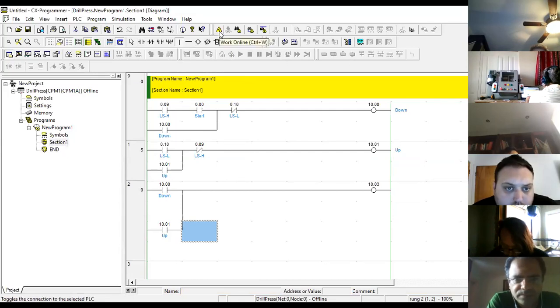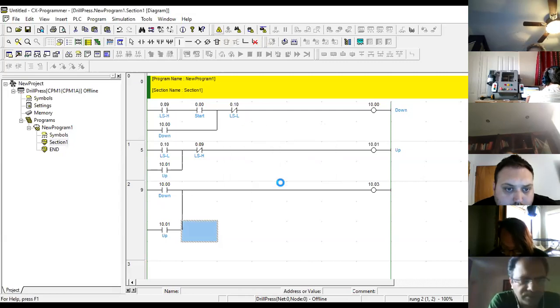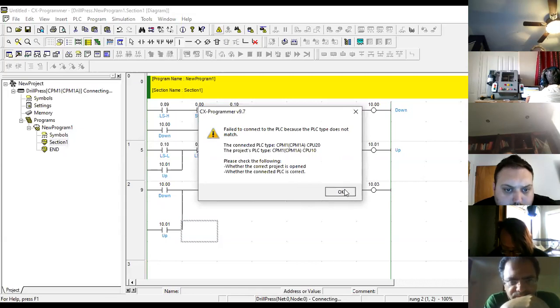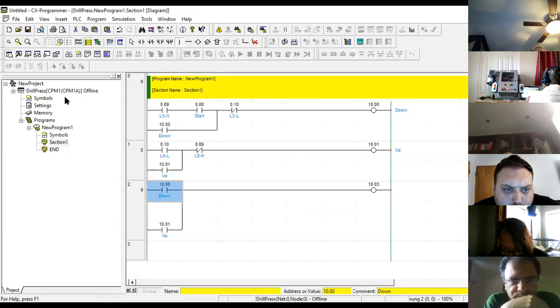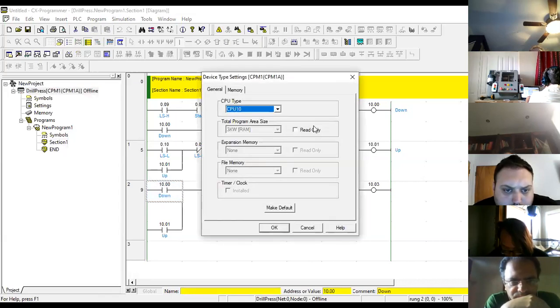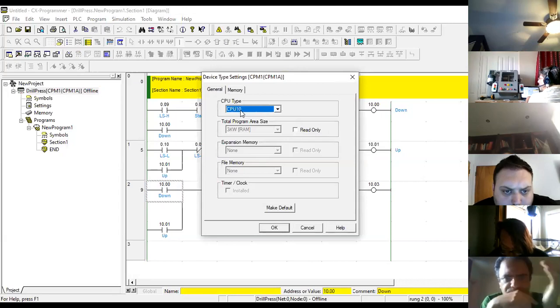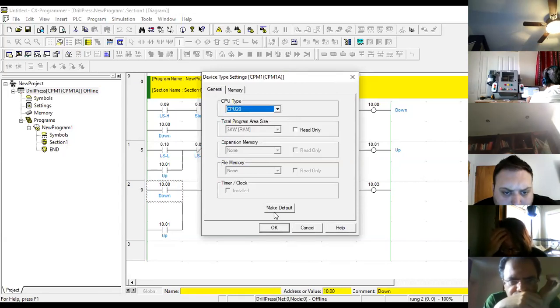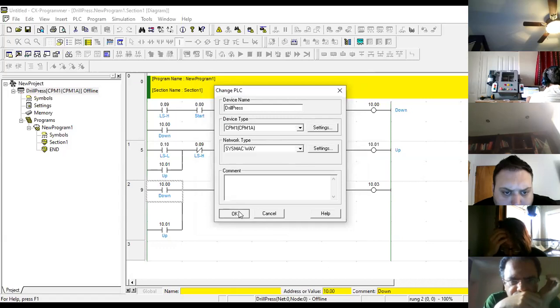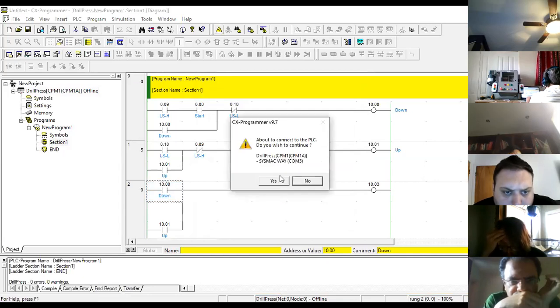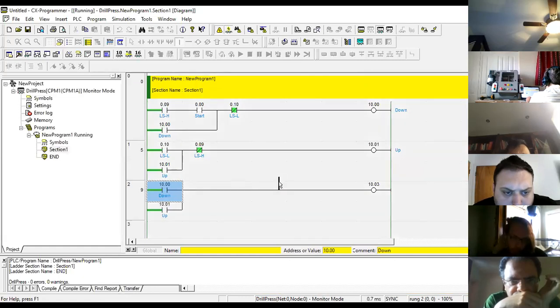So we're going to download it and see what happens. I'm going to click on this little icon here, which opens up a port for communication. It'll tell you if you have certain errors, not all errors. Oh, failed to connect. There's one thing that I forgot to do. We have two PLCs that we're using. We have to choose the correct one. Remember when I talked about CPU 10 and CPU 20, the one I have right now is a CPU 20. So you have to have the right one. Otherwise it won't be able to communicate.